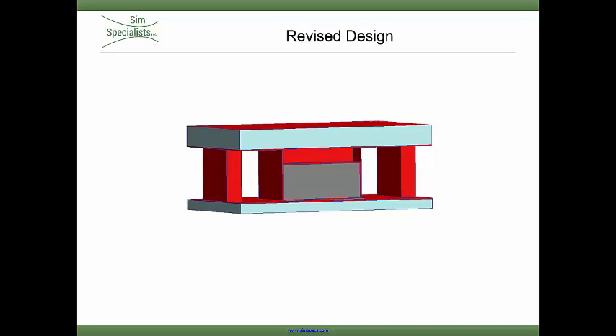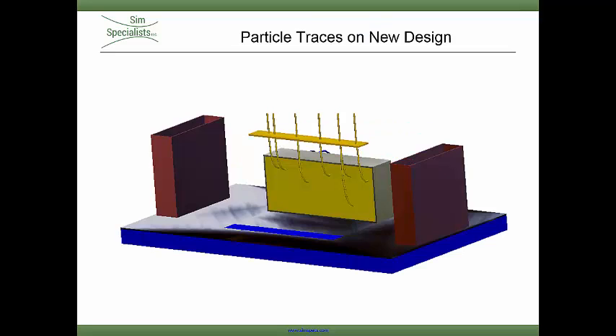A second design will be considered with hot aisle containment to force air directly back to the CRAC units after passing through the servers and going up into a suspended ceiling, without any opportunity for recirculation. As expected, the flow is now directed through the servers and up into the ceiling.